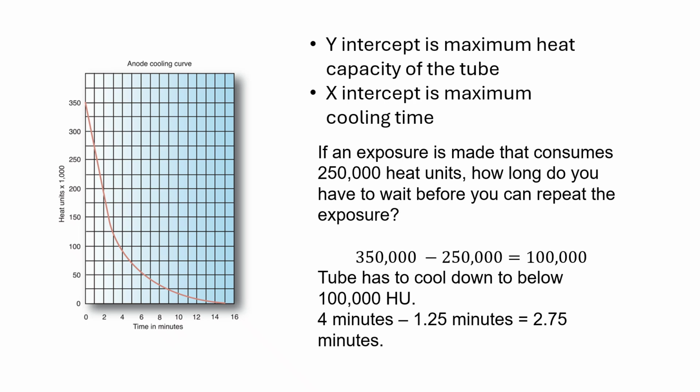And it'll give you 3 different techniques, and you'll have to calculate the heat units for those 3 different techniques using the heat units formula, and then figure out which one you have capacity for still. Okay? In this case, it would be a technique that resulted in less than 100,000 joules or 100,000 heat units.